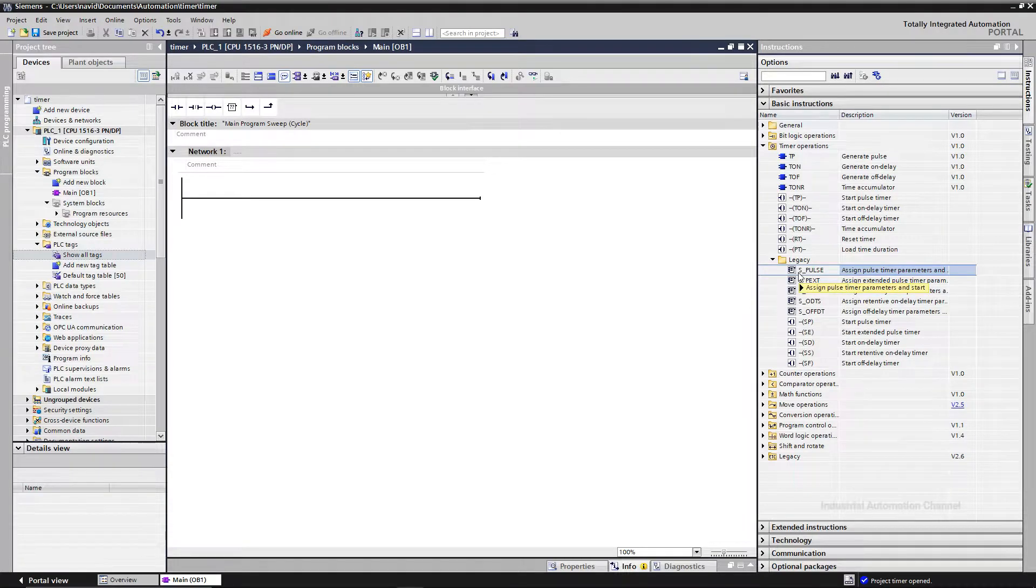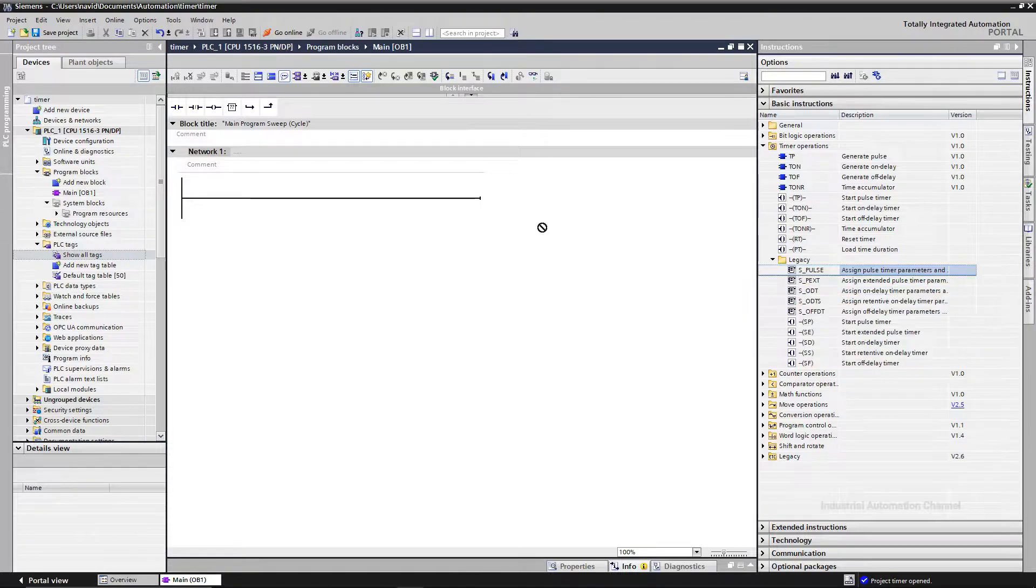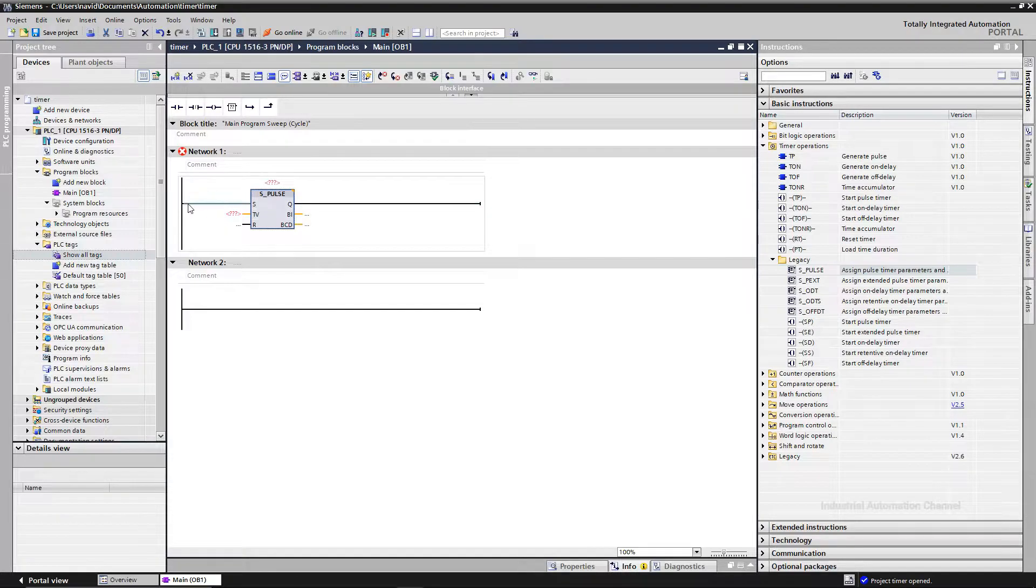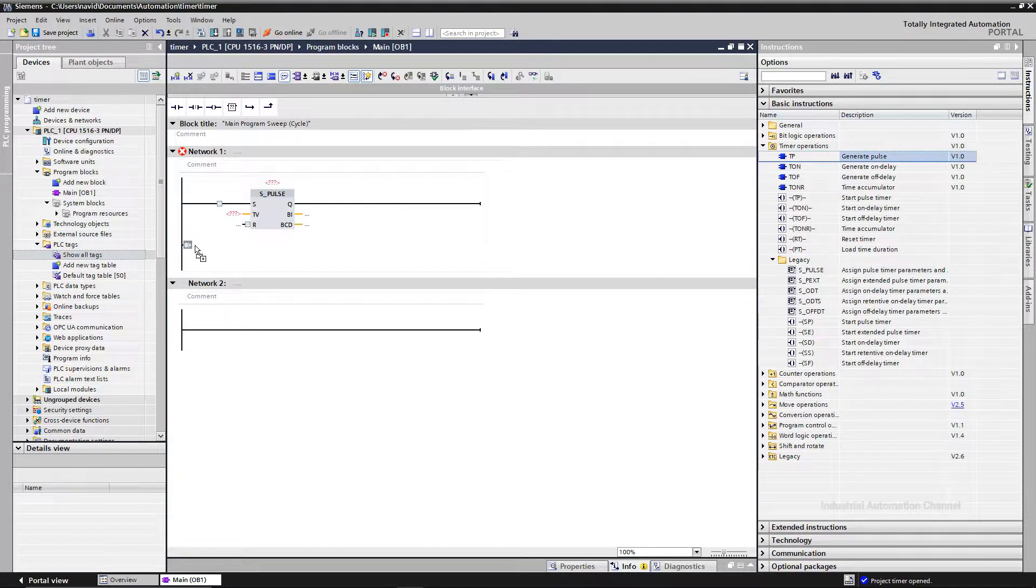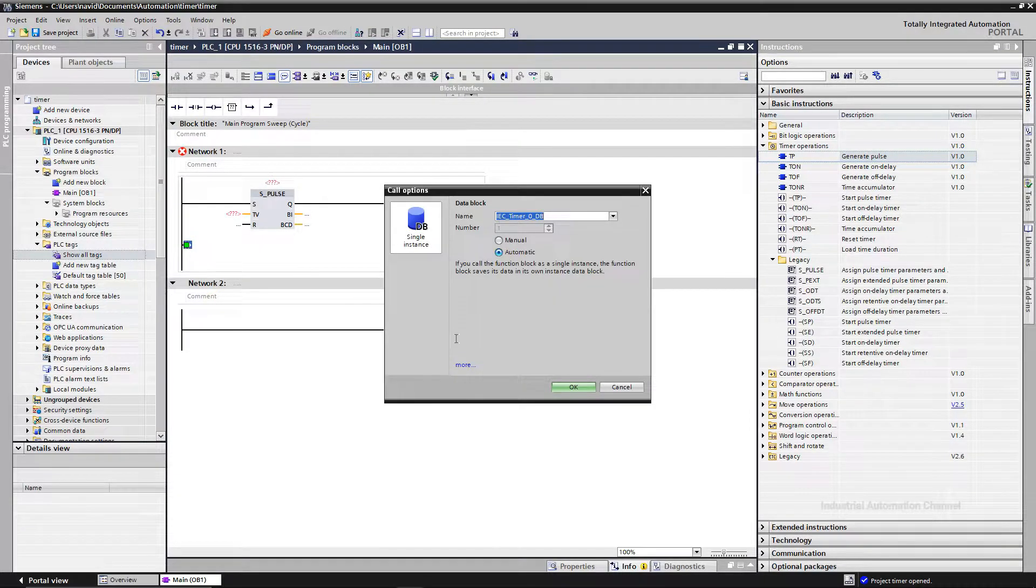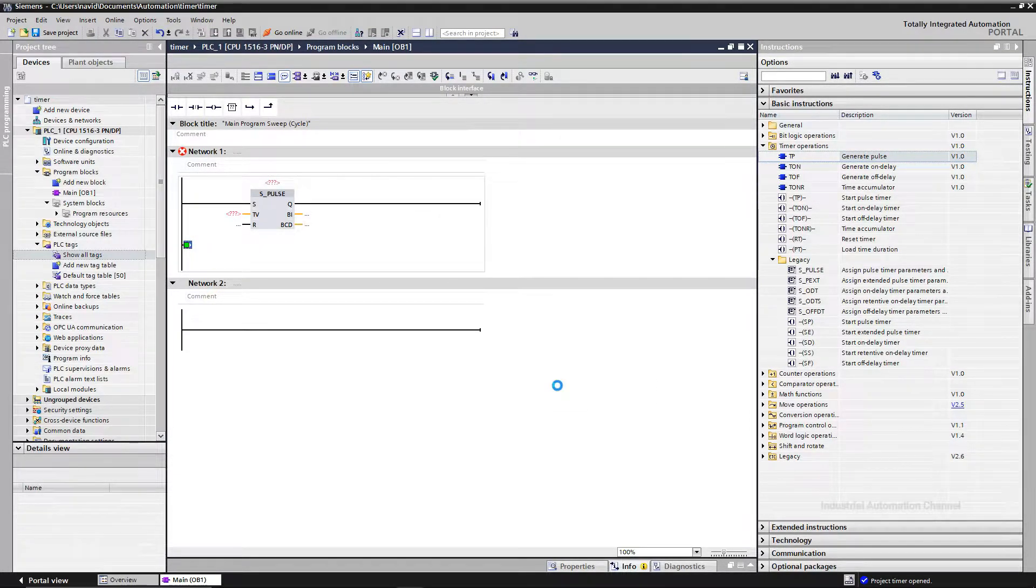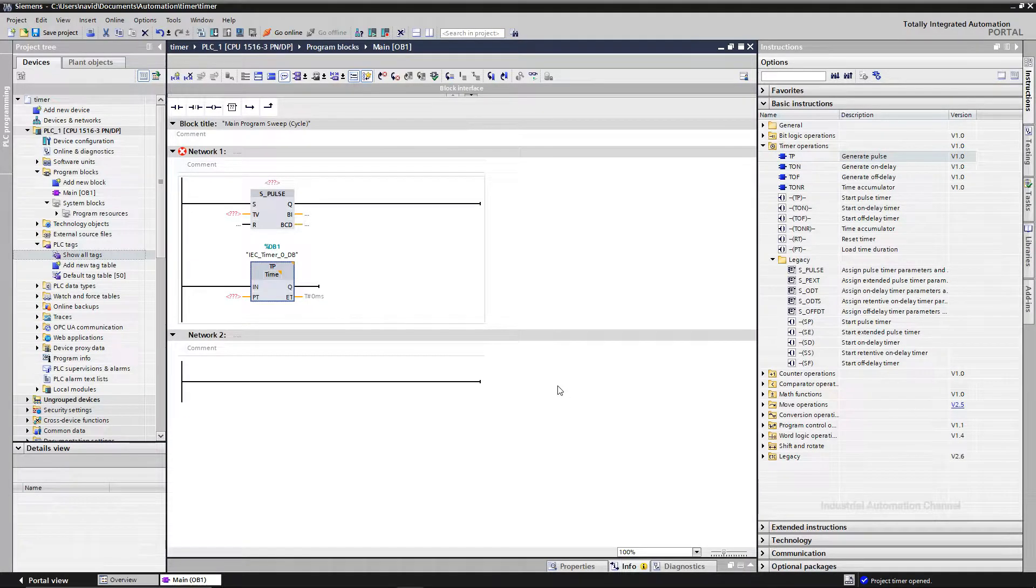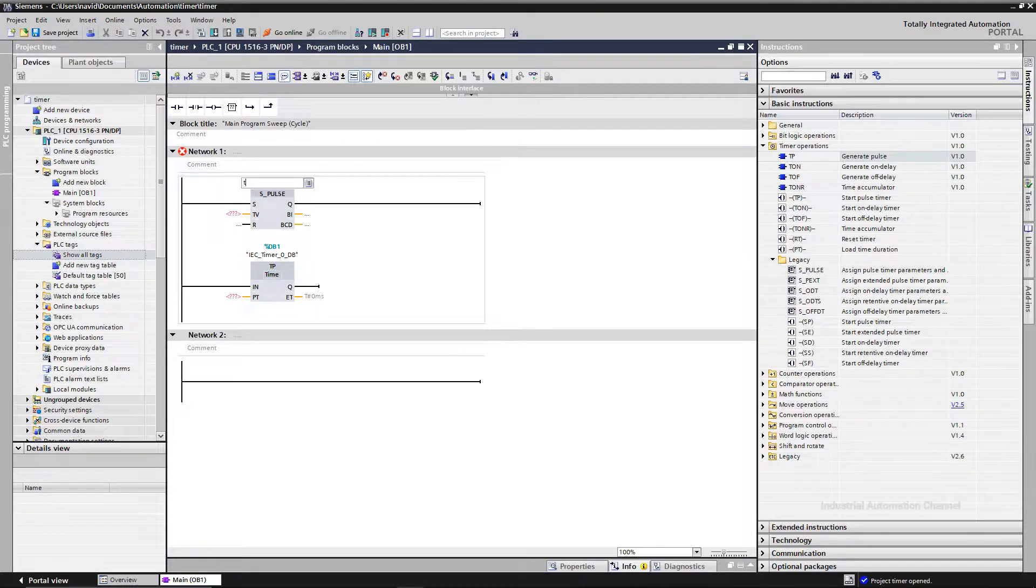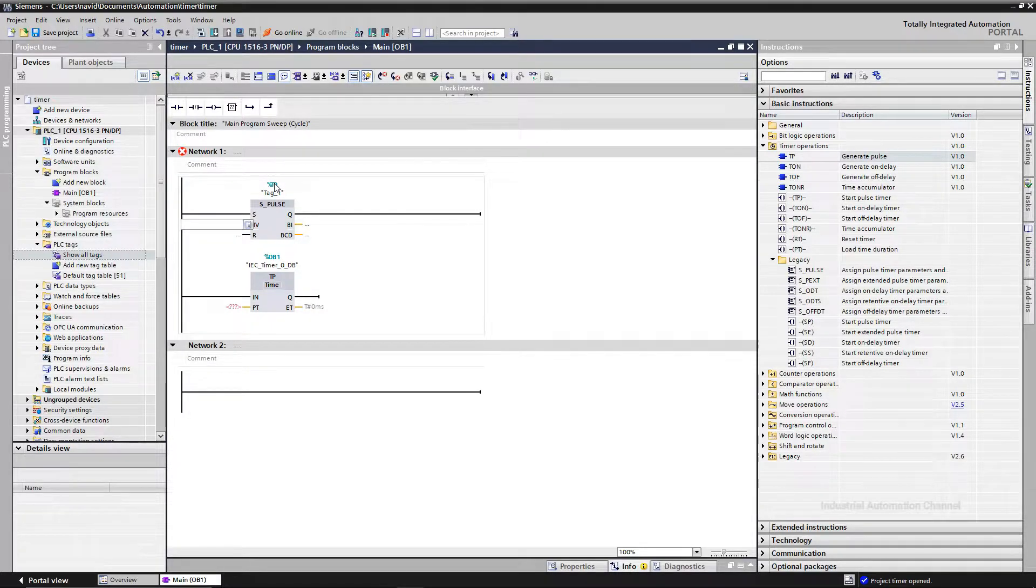The first timer is S_PULSE. It's like a TP timer of IEC. Let's insert it into our program. And the TP timer to see the difference between these two timers. If you insert an IEC timer, TIA Portal automatically creates the data block required for the data saving. But it's different for S5 timers. They are addressed absolutely via a letter T and a number. T0, T1, T2.